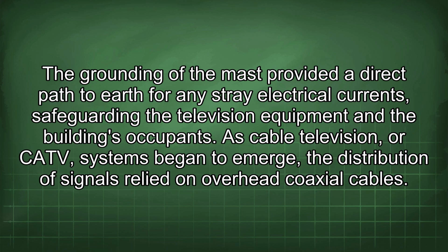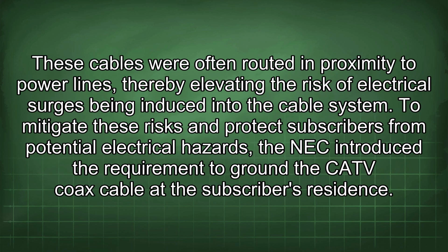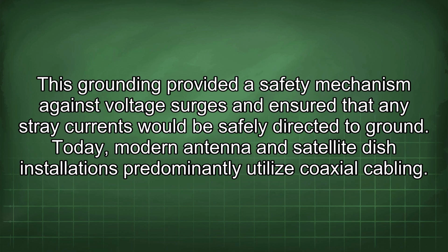As cable television, or CATV, systems began to emerge, the distribution of signals relied on overhead coaxial cables. These cables were often routed in proximity to power lines, thereby elevating the risk of electrical surges being induced into the cable system. To mitigate these risks and protect subscribers from potential electrical hazards, the NEC introduced the requirement to ground the CATV coax cable at the subscriber's residence.